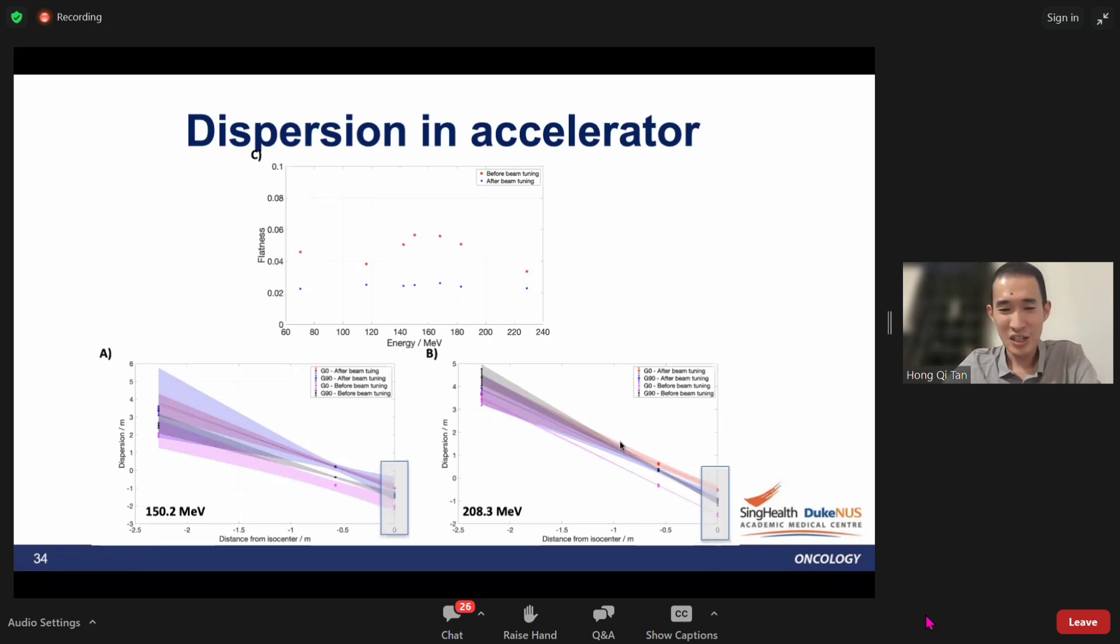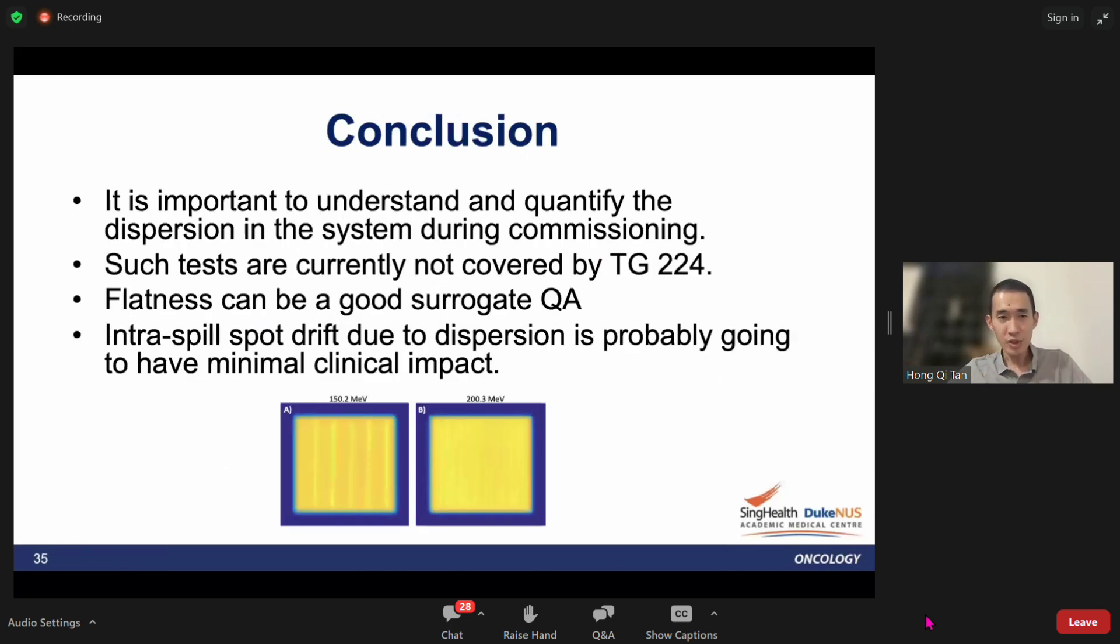Showing the dispersion measurement helped convince the Hitachi engineer to do something about the tuning, and in the end you get better beam qualities and better treatment plans for the patients. In conclusion, we think it's important to understand and quantify the dispersion system during commissioning. You don't have to do it as periodic QA—it's very time consuming—but it should be understood first during commissioning. Such tests are currently not covered by TG-224.